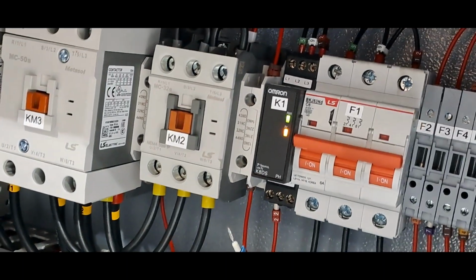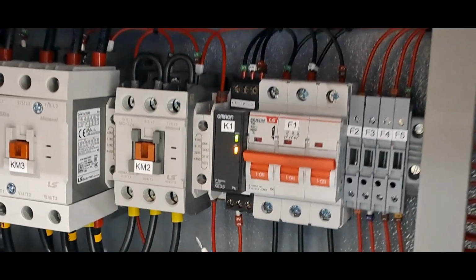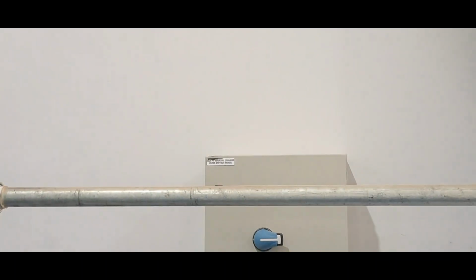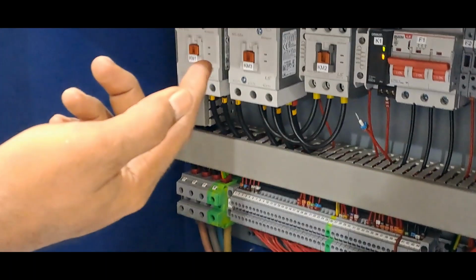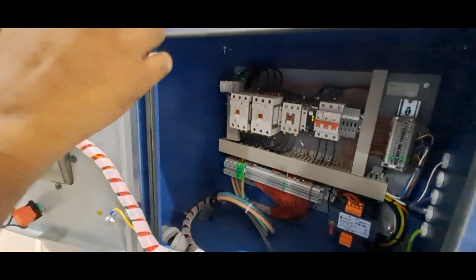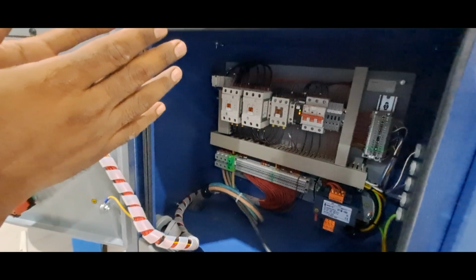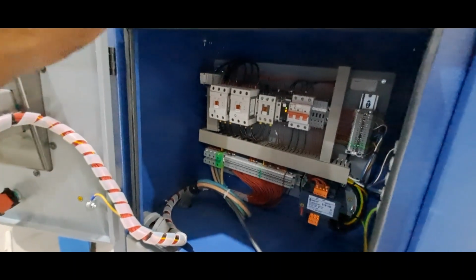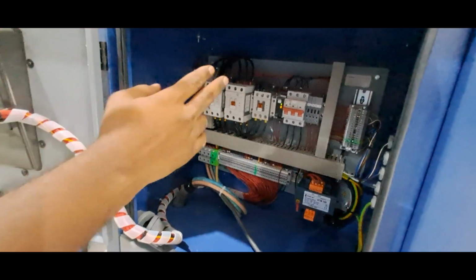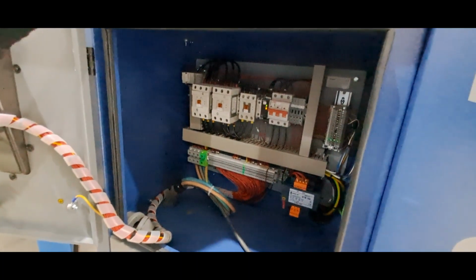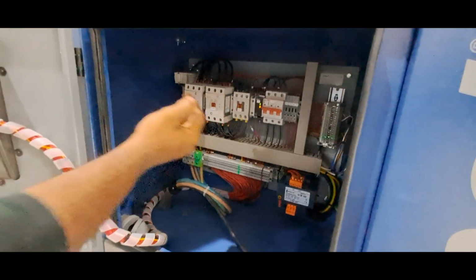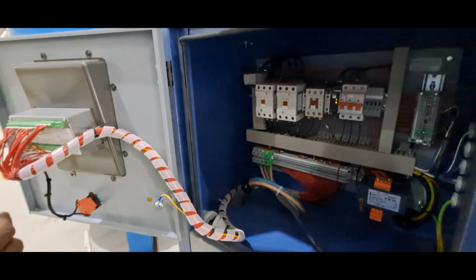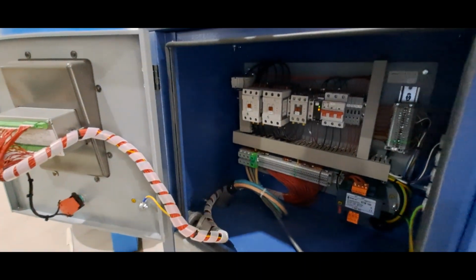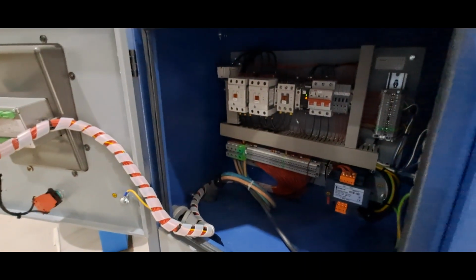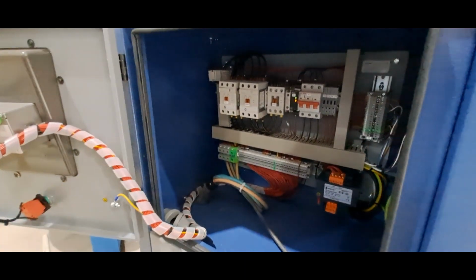If there is no phase in one line, that means you have to check from your isolator or in your MDB, the power source. Also one more thing, with this relay, if the phase is interchanged, even if you are getting proper voltage and there is no voltage drop, and all three R, Y, B are okay, if the phase sequence is interchanged from the MCB, then this same error will come. So we have to interchange two phases from the main incoming, then this error will be gone.